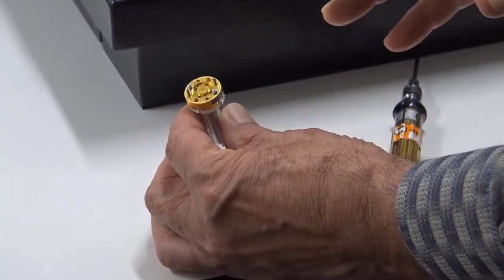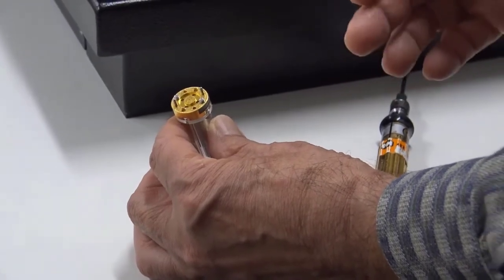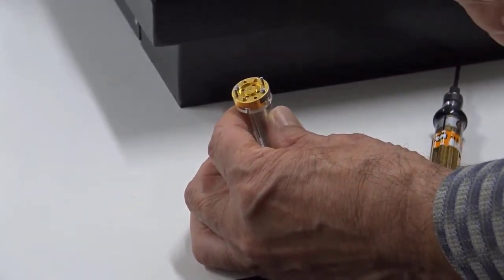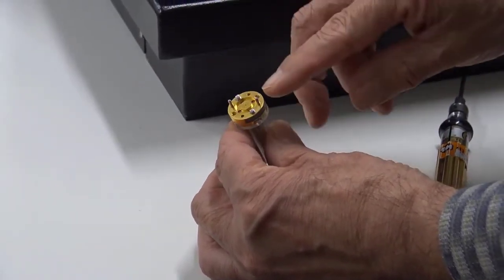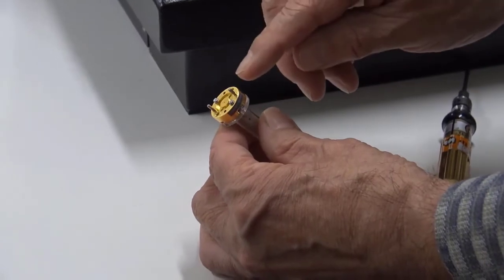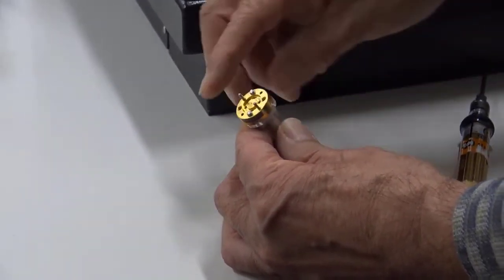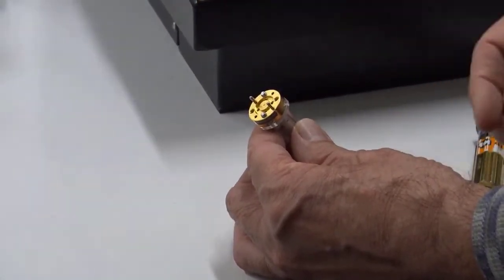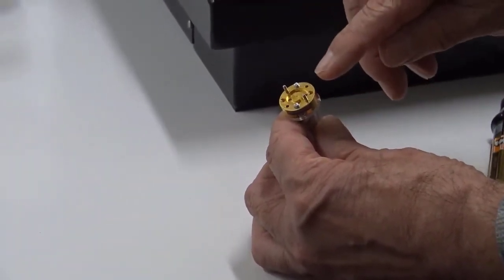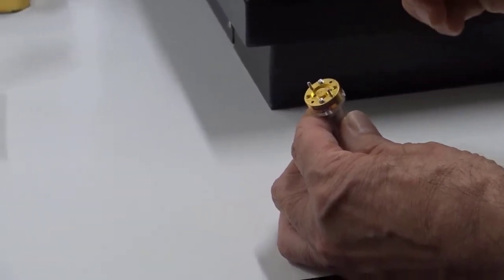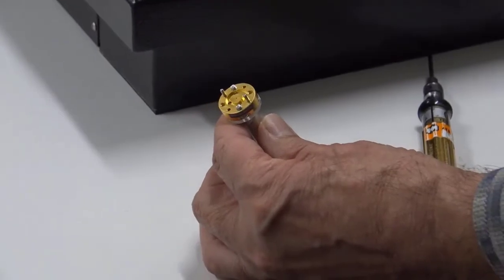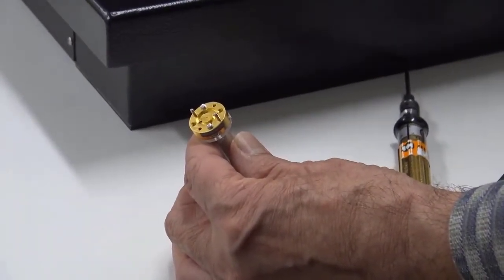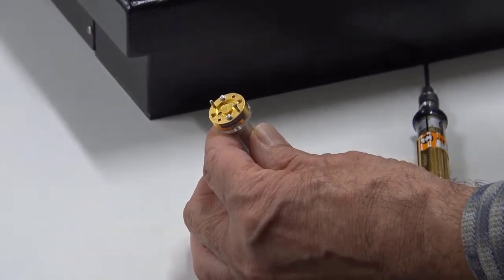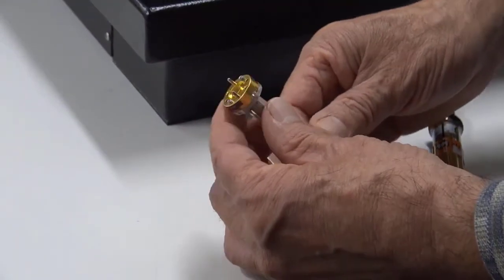Okay, so I mentioned the center pin, and in this case it's a 0.6 millimeter airline coaxial interface. On the probe side, there is a male pin, and it has a slight protrusion from the base. And with these guides, you have some protection, but you do want to be aware of the fact that there is a positive pin depth to the male pin on the probe itself. On the module, the female is recessed in. Okay, and so you see that there are the two guides, and then we have this cover.